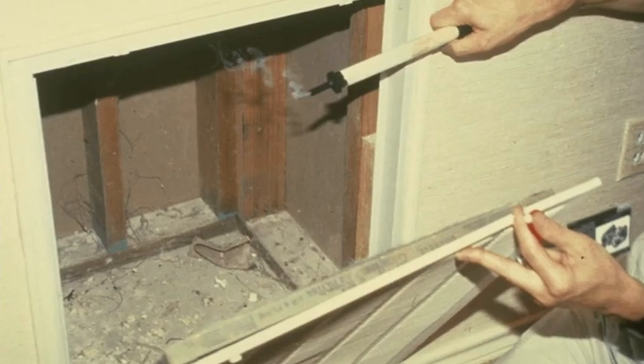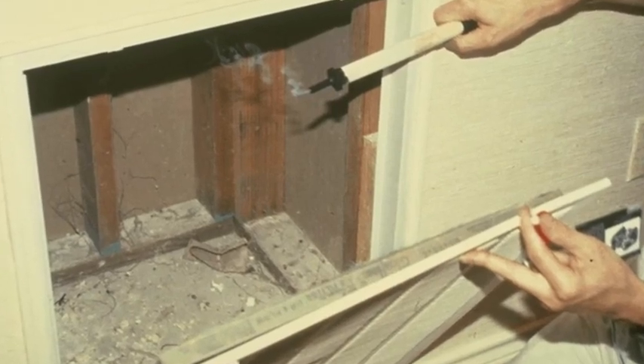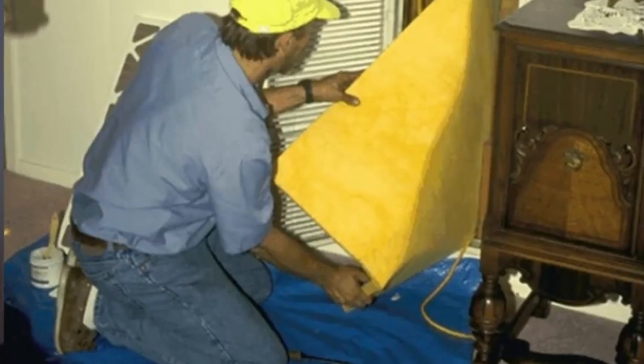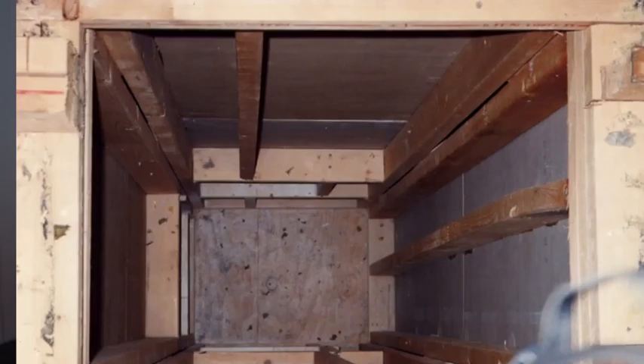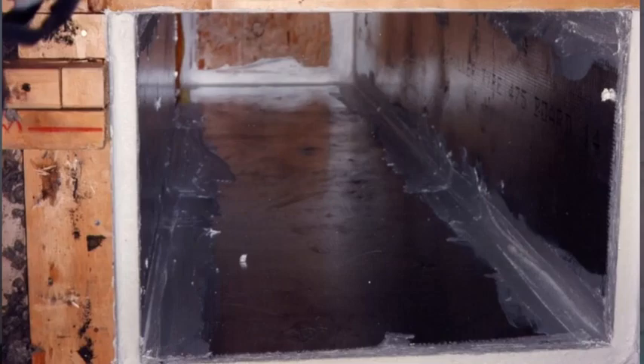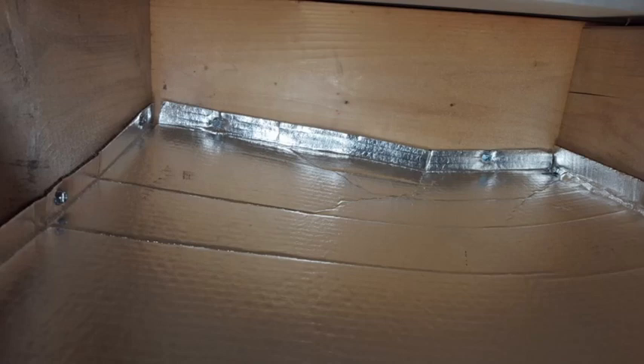Another style is a large building cavity chase behind the grill that carries the air up or down to horizontal equipment in the attic or crawl space. AeroSeal can work on these as well, or if the gaps are too large, the chase can be lined with ductboard or thermopan cardboard. AeroSeal dealers either hand seal these or they mechanically attach the damming and then inject AeroSeal to seal the remaining cracks. Some AeroSeal dealers will price their jobs to just include fixing these when they run into them. Others have an add-on on their price list.